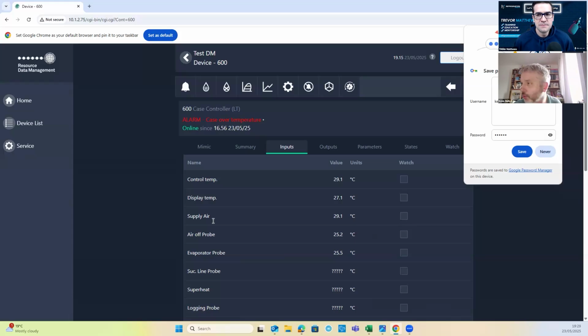So, classic example is cold stores. RDM calls all its alarms case. Even if I change that to a cold room, it will still say case over temperature when it alarms. But I can do an alias change through this panel, and I can change that to say cold store high temperature. And it's all about what your customers want to see. You know what the customer's going to see. If they're really on it, they're going to go, why does it say case over temperature? It's a cold store, right?